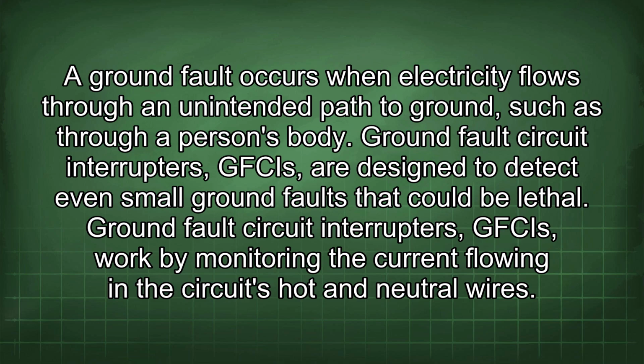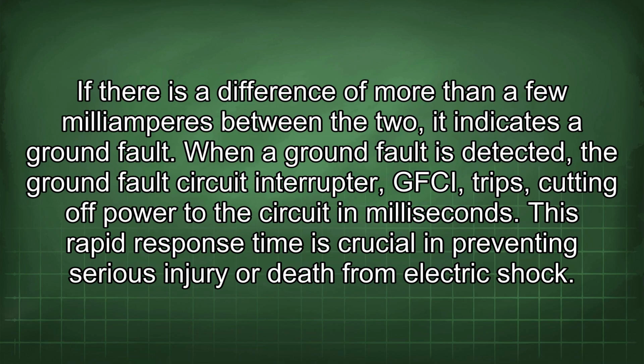A ground fault occurs when electricity flows through an unintended path to ground, such as through a person's body. Ground fault circuit interrupters, GFCIs, are designed to detect even small ground faults that could be lethal. GFCIs work by monitoring the current flowing in the circuit's hot and neutral wires. If there is a difference of more than a few milliamperes between the two, it indicates a ground fault. When a ground fault is detected, the GFCI trips, cutting off power to the circuit in milliseconds. This rapid response time is crucial in preventing serious injury or death from electric shock.